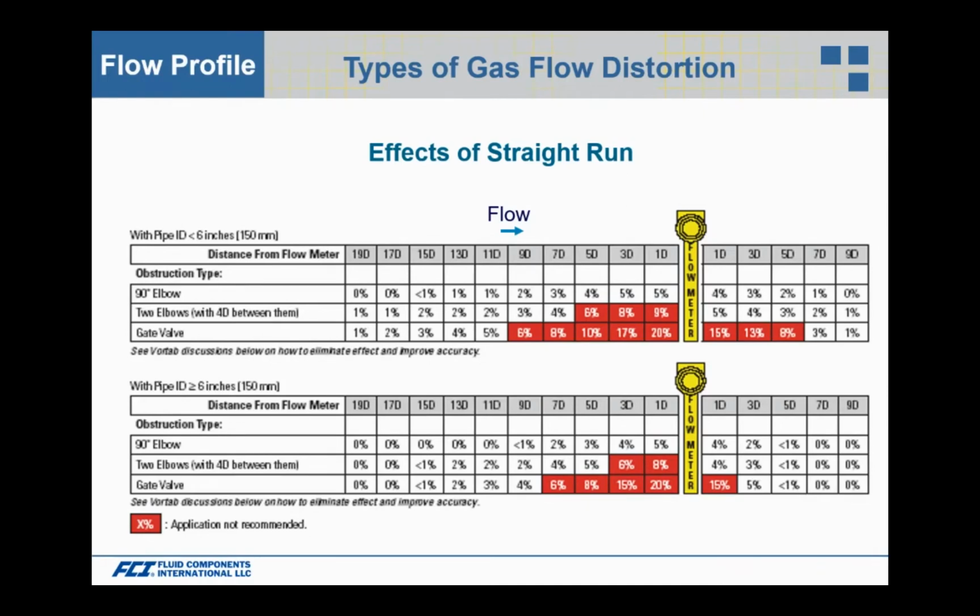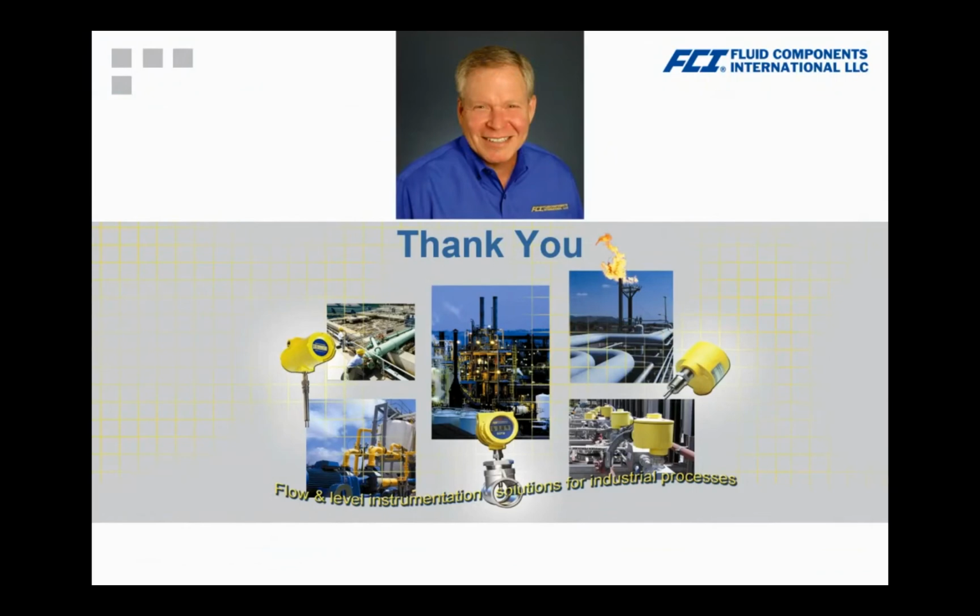Insertion of the probe all the way inside the pipe and pulling it back half of the ID, could it be a good installation for the flow element? Say that one more time, I'm sorry. So I guess inserting the probe all the way to the end of the pipe and then retracting it, is that a good way to find the middle of the pipe? Actually, the probe has measurement graduation marks, marked in inches and metric. So if you have a 6-inch pipe, you only need to know the nozzle height, and you can add 3 inches, and then we like to go half an inch past center line. So half inch plus the 3-inch half-pipe ID plus the nozzle, let's say it's flanged at 6 inches. Therefore, we know that we need to go 9.5 inches. On the probe, you can take a marker, mark 9.5 inches, and insert it down to that mark.